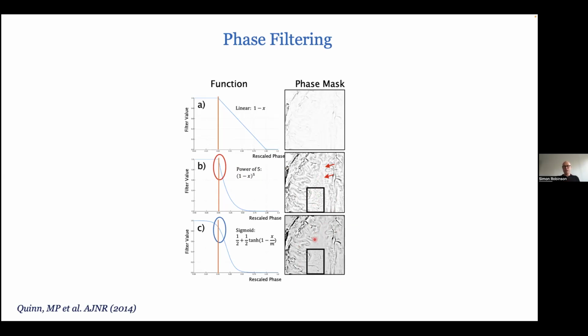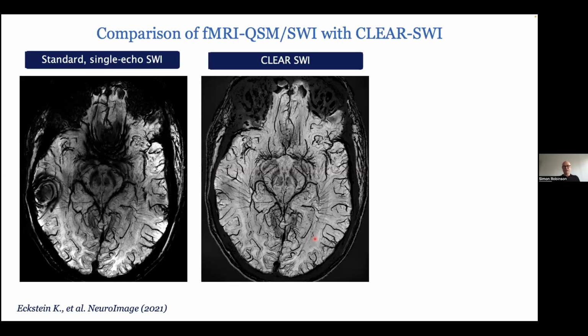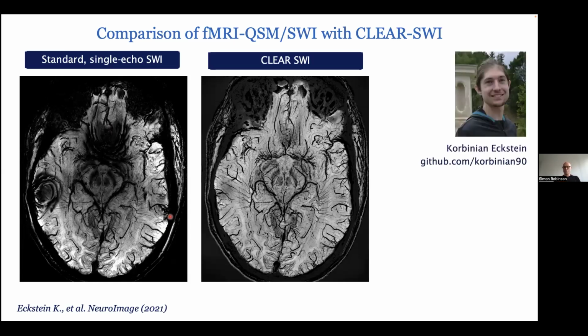Okay, so we've pieced all of those steps together, and we end up with this considerable improvement in SWI at 7T compared to the vendor single echo version. It's also got the advantage that because it's multi-echo, we can generate R2 star maps for it, which we do, and M0 images, and all of this runs on the image reconstructor. So we bundle this now with ASPIRE to run on the same platforms. So I don't know how many people are using this now, but it's available to everyone who has adopted our ASPIRE C2P. Okay, so that's an example from a healthy subject, 7T.